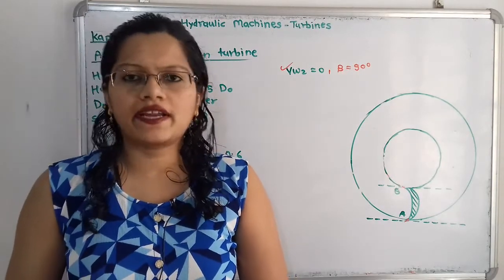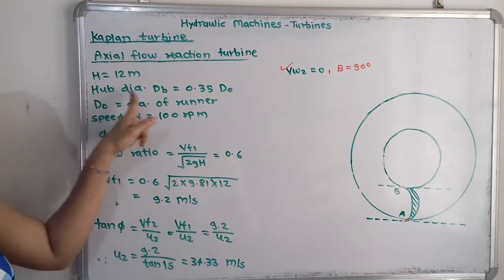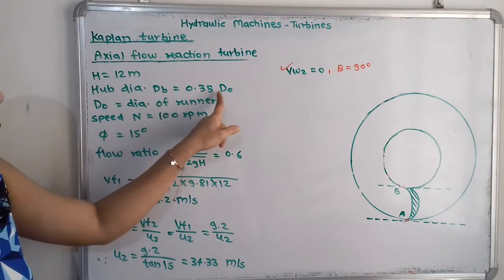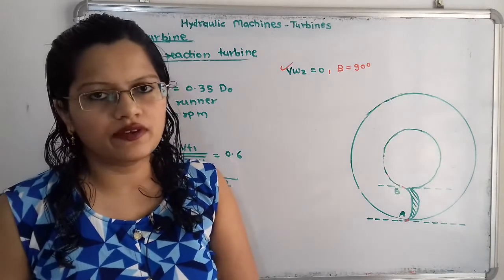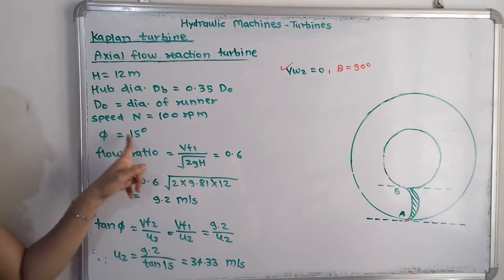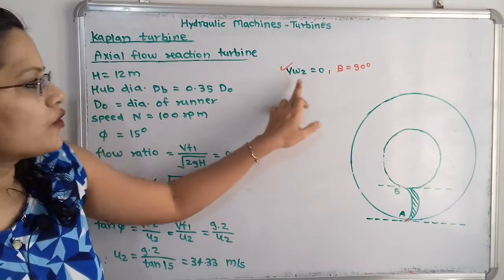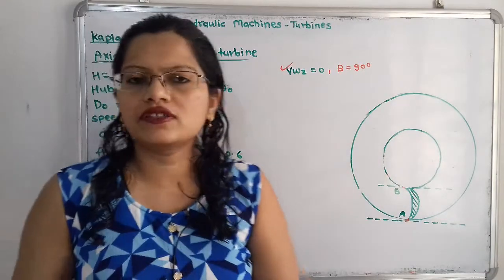Let us first note the given data and draw the velocity diagram. Head H = 12 m, hub diameter db = 0.35 × Do (where Do is the diameter of runner), speed N = 100 rpm, vane angle phi = 15 degrees at outlet tip. Since the velocity of whirl at outlet vw2 = 0, it follows that angle beta = 90 degrees. We will draw the velocity diagram at the outlet tip based on this condition.